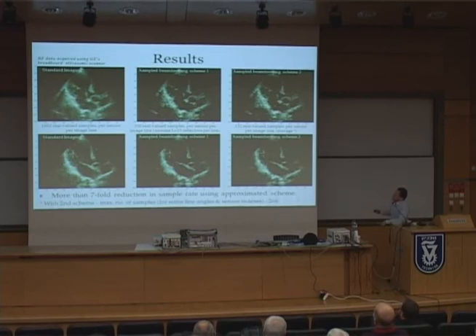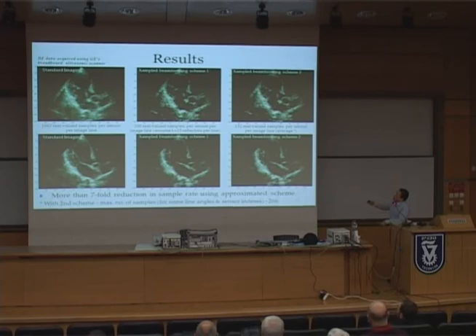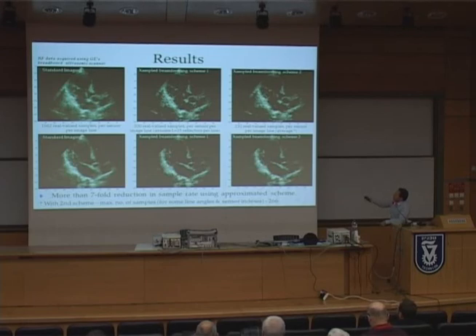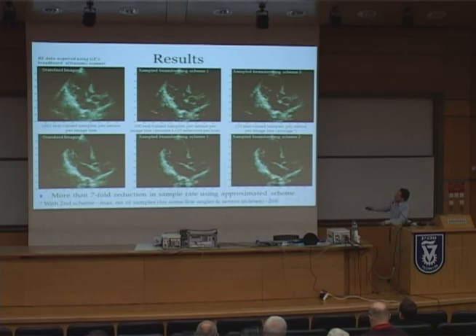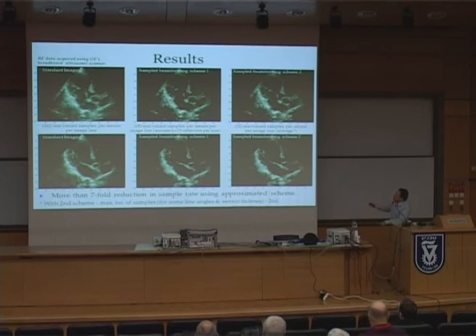These are some results obtained using both our schemes. The data was obtained from GE's breadboard ultrasonic scanner. In the left column are two frames of cardiac imaging generated using standard imaging techniques. The middle and right columns were generated using our first and second schemes respectively — the second scheme approximating the first. The images resemble one another very well, and both schemes successfully recover the strong perturbations visible in the standard image. These images were obtained at more than a sevenfold reduction in sample rate, which is quite impressive.